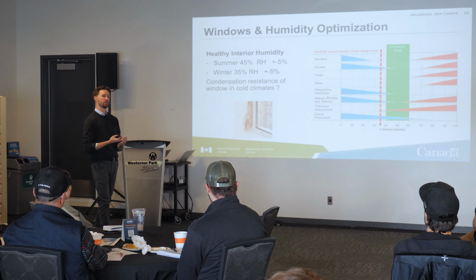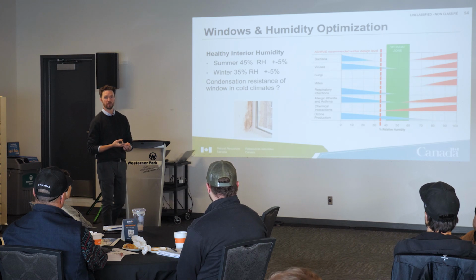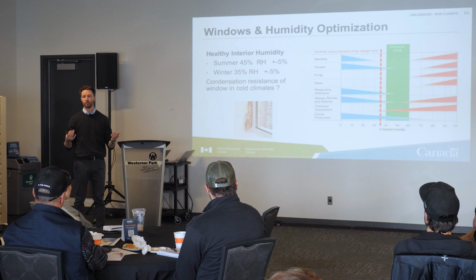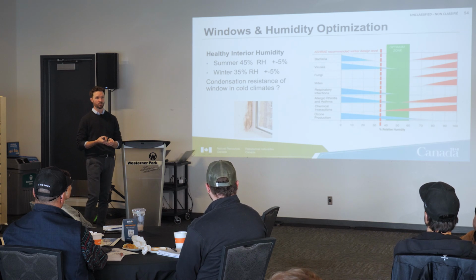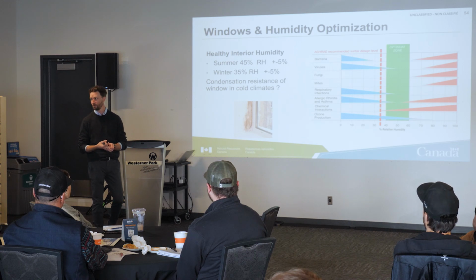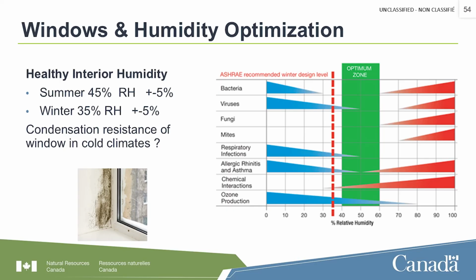Typically we don't want to lower interior humidity too much, for a number of reasons. What do homeowners want? Higher humidity. What do hardwood manufacturer warranties want? Higher humidity too. So there's a lot of reasons not to drop humidity down to 20% in winter, even though that would help our condensation issues quite a bit.